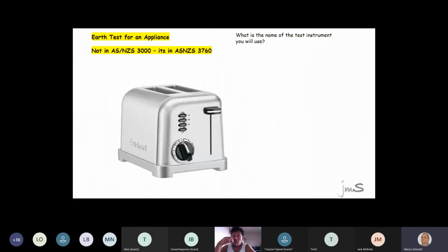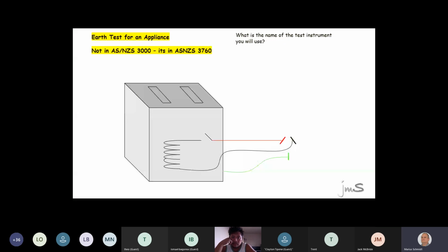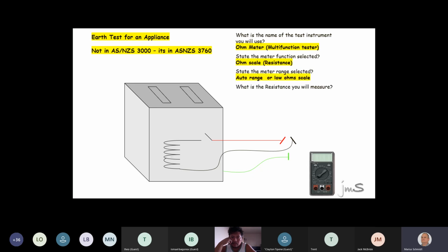Cool. Now, if I give you a toaster. Now, this book is not given to you. They expect you to know this. There's a standard called 3760, which will tell you. Now, all Supermans and Supergirls, look at my toaster. If you see inside, it looks like that, eh? So you take your ohm meter, put it at the beginning and end, from the earth to the casing, and you press test. What's the maximum value you'll get? Is it A, low enough to operate the protection device? B, half an ohm? Or C, 1 ohm? Maximum 1 ohm. Do you remember appliances 1 ohm or less? Do you know that the extension lead needs to be 1 ohm or less?